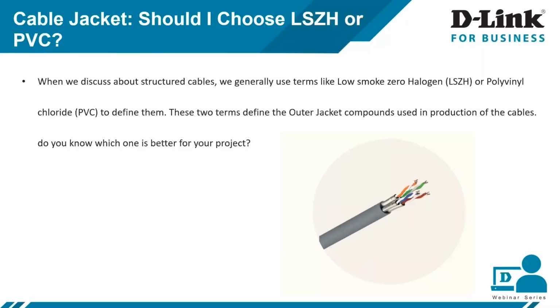This will change the entire thing, because if you see surveys across the world, so many people die because of fire, or probably because of the smoke. 60 to 80% of people are dying because of smoke in case of fire, so it becomes very, very important. Low smoke zero halogen would be much safer and more reliable for places where fire presents a hazard to the occupants.